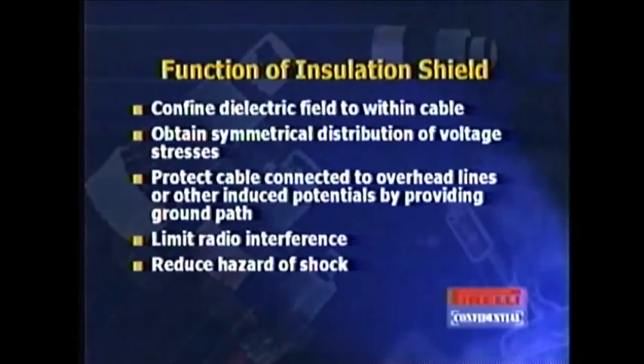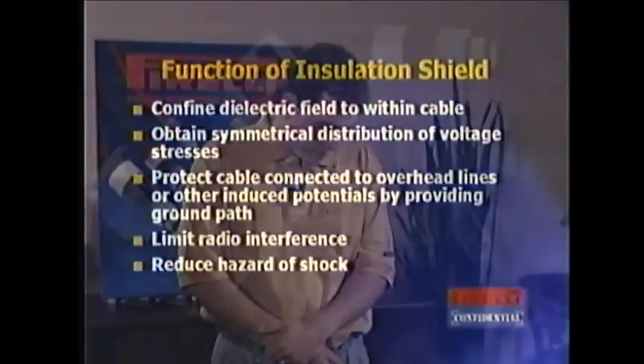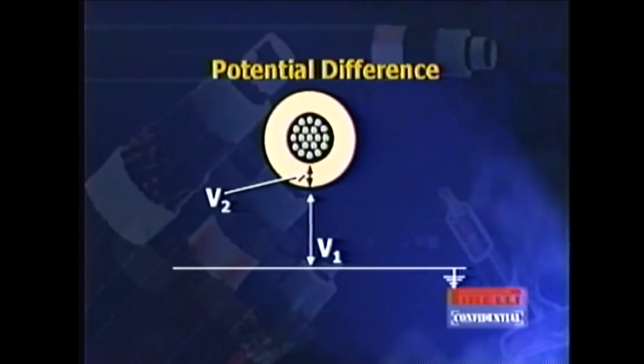The purposes of this insulation shield, number one, is to obtain symmetrical distribution of the voltage stresses, as we said. Another one is to protect the cable connected to overhead lines or other induced potentials by providing some type of a ground path. This assumes that that's grounded, and we'll talk about that in a second. Another function of the insulation shield is to limit radio interference and also to reduce the hazard of shock. Now, as we implied before, if you have a conducting material around the circumference of the cable, the point of that is to make sure that you have that at some constant potential. Because if you don't, you'll have a potential difference between that conducting material and the ground plane.